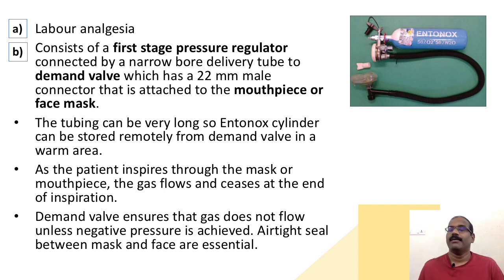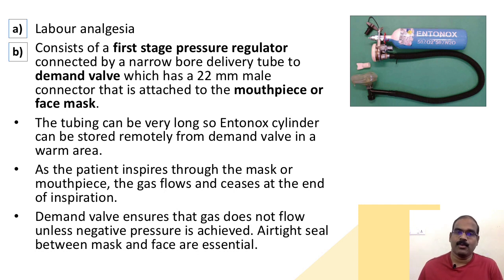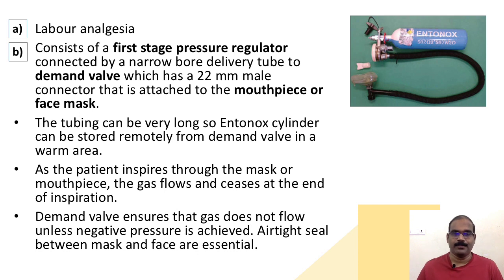The demand valve has a 22 mm male connector attached to the mouthpiece or face mask. The advantage is the tubing can be very long, so the Entonox cylinder can be placed remotely from the demand valve in a warm area. As the patient inspires through the mask or mouthpiece, the gas flows and ceases at the end of inspiration, so the demand valve ensures gas does not flow unless negative pressure is achieved. An airtight seal between the mask and face is essential.